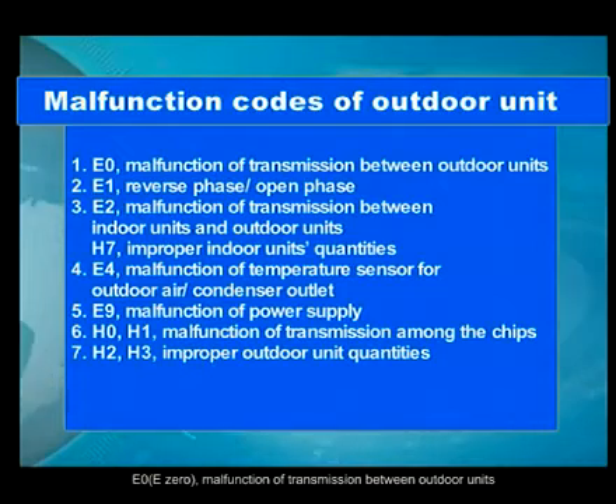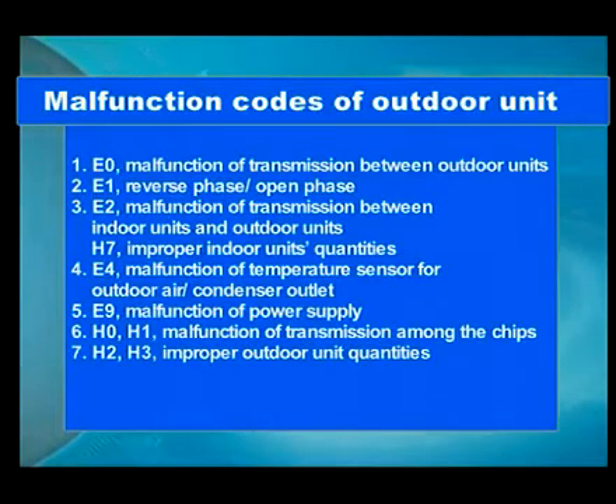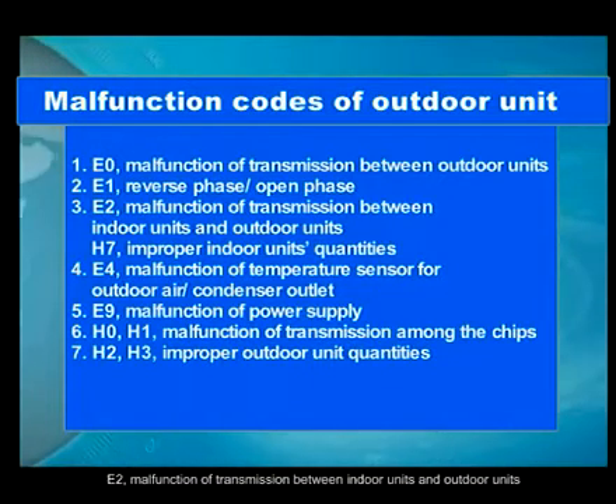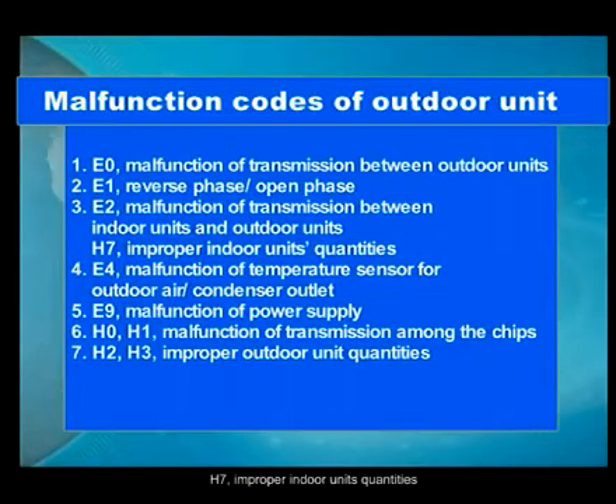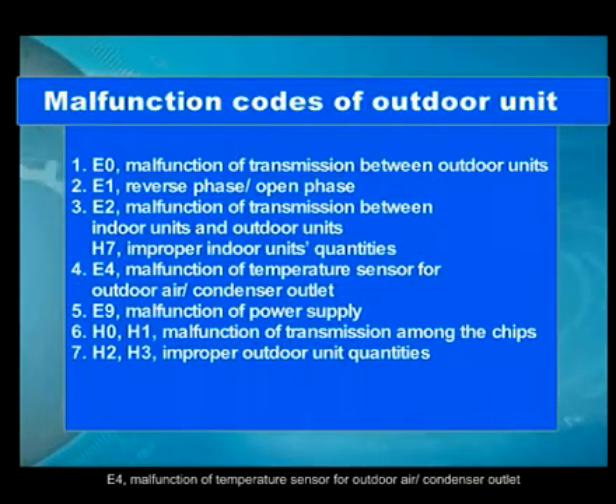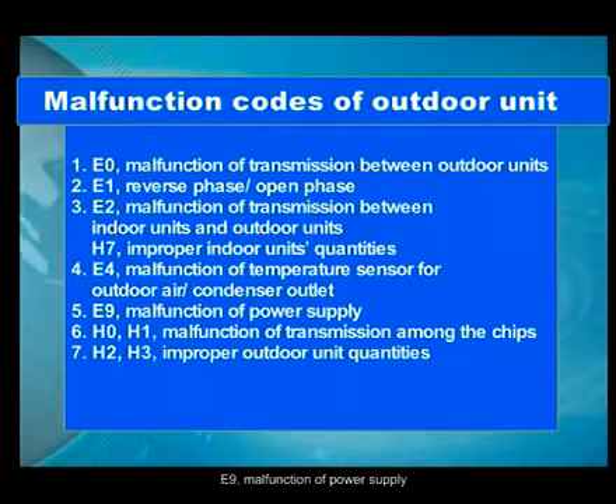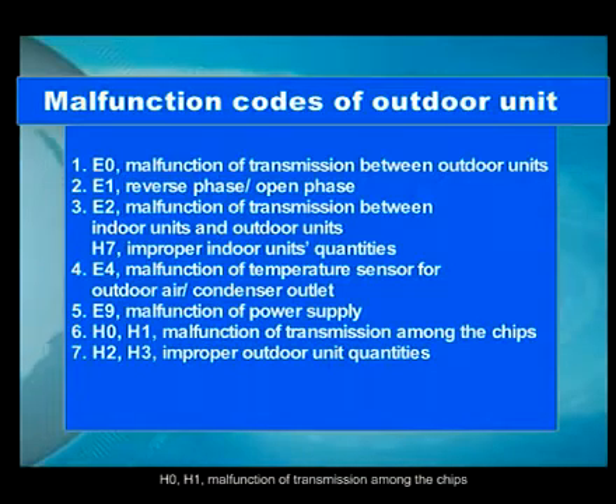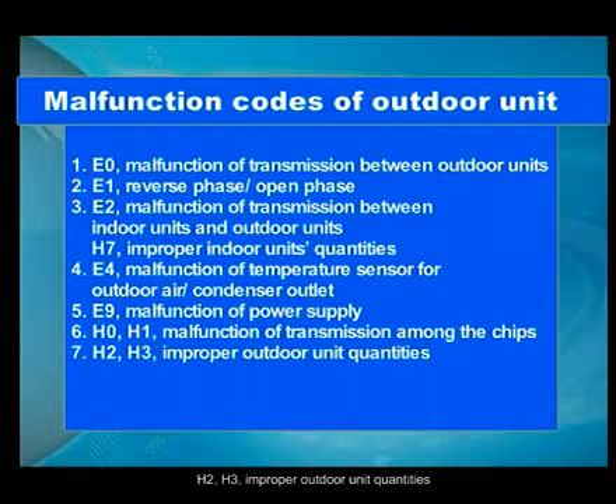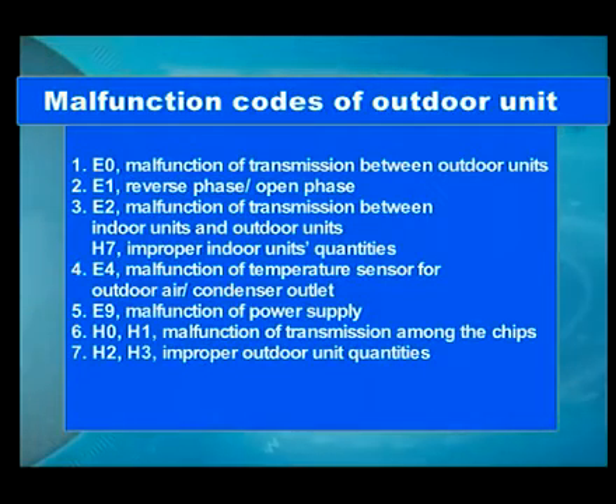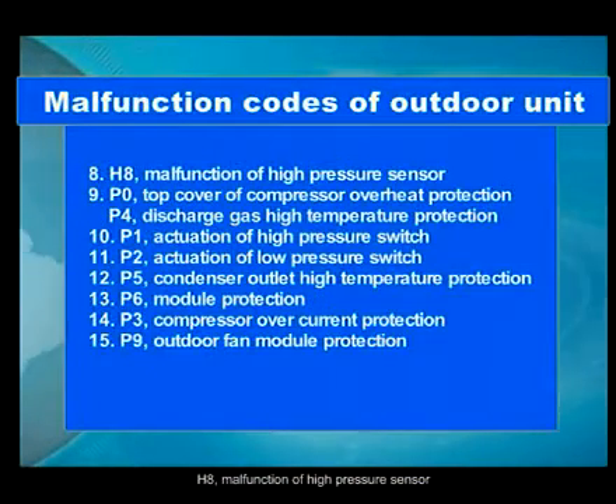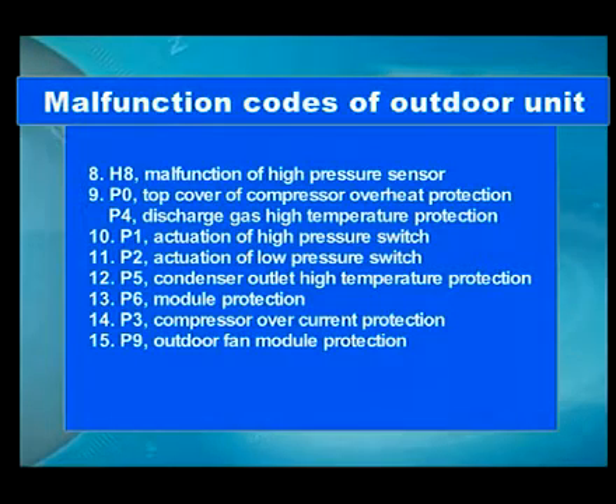E0. Malfunction of transmission between outdoor units. E1. Reverse phase/open phase. E2. Malfunction of transmission between indoor units and outdoor units. H7. Improper indoor units quantity. E4. Malfunction of temperature sensor for outdoor air/condenser outlet. E9. Malfunction of power supply. H0, H1. Malfunction of transmission among the chips. H2, H3. Improper outdoor unit quantities. H8. Malfunction of high pressure sensor.